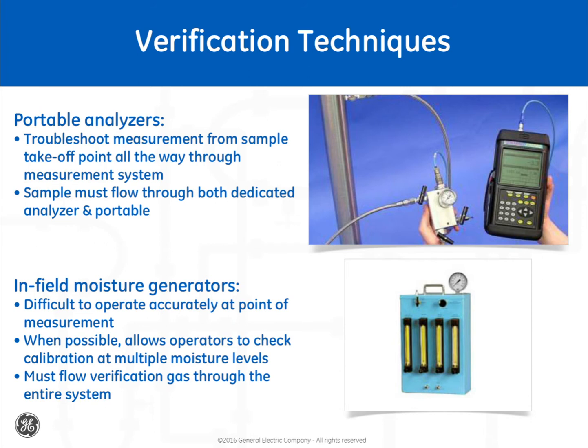The key to success is that the sample that passes the portable analyzer should be the same sample that passes by the dedicated analyzer, preferably in series, directly after the sensor to be verified. This method allows the operator to verify the measurement at the moisture content that is meaningful to the customer.